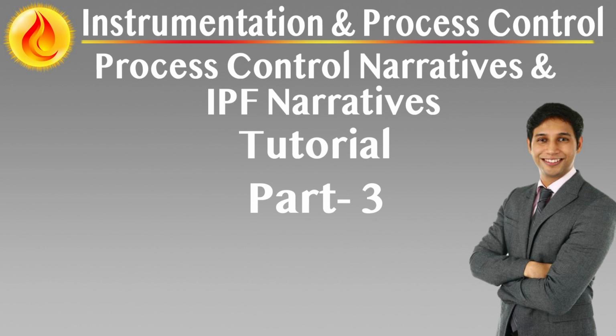Alarm classification and system integration. During the implementation phase, alarm narratives support classification by helping assign alarm priority, e.g. high, medium, low, alarm category, e.g. safety, equipment protection, environmental, operational, and suppression rules or filters, e.g. based on mode of operation. All alarm settings, such as limits, deadbands, delays, and priorities, are maintained in the plant's instrument configuration database, e.g. InTools or Delta V database, not in the narrative. However, the rationale for settings and categorization originates from the alarm narrative.